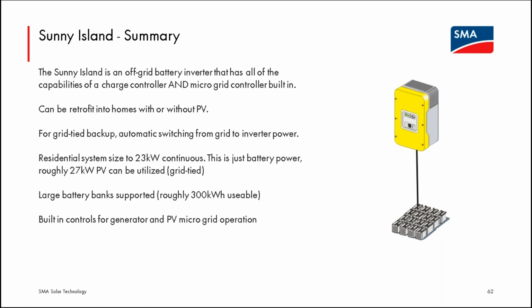But the Sunny Island, again, in summary, should be considered a battery-based inverter that is usable as off-grid or grid-tied battery backup. It can be used without PV, retrofit into a system with PV, or added at the same time as PV. It has quite a bit of capacity just from the Sunny Islands for battery power, so it really is capable of whole home backup and can access very, very large battery banks. So with that, any questions that I can handle?